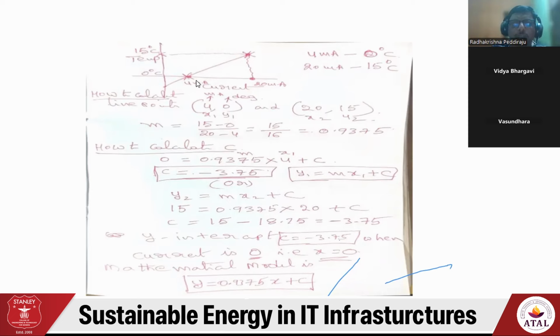So here I have taken 4 milliamps to 20 milliamps. Why take 4 to 20, why not 0? This question also comes. If you take 0, the problem is: if the sensor fails, 0 current comes, and we don't know whether it's because of 0 current failure or 0 degrees temperature. That's why we call it offset values, so design an offset value.